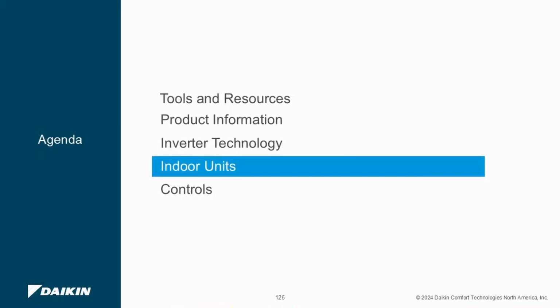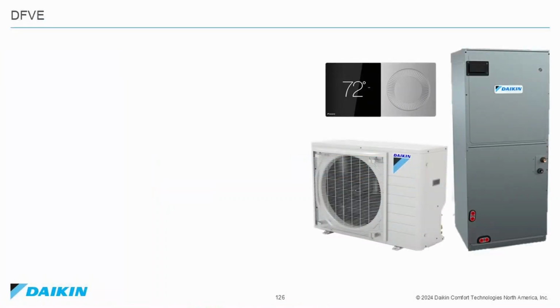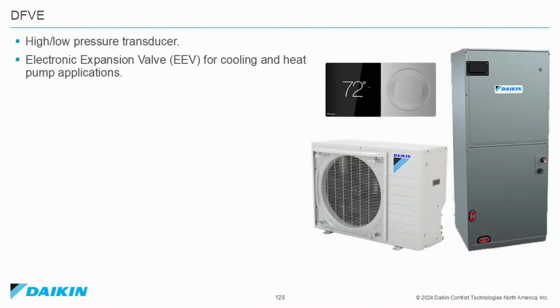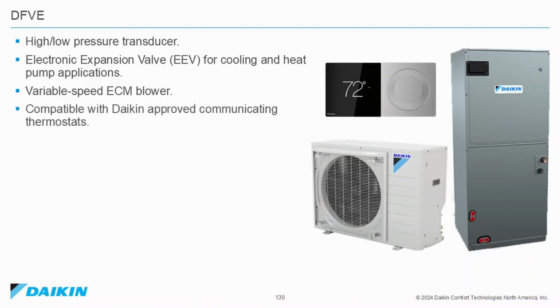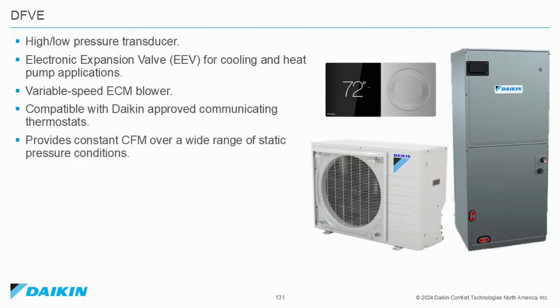Indoor units. The DFVE air handler. High and low pressure transducer. Electronic expansion valve, or EEV, for cooling and heat pump applications. Variable speed ECM blower motor. Compatible with Daikin-approved communicating thermostats. Provides constant CFM over a wide range of static pressure conditions. Horizontal and vertical configuration. 7 mm coil tubing.